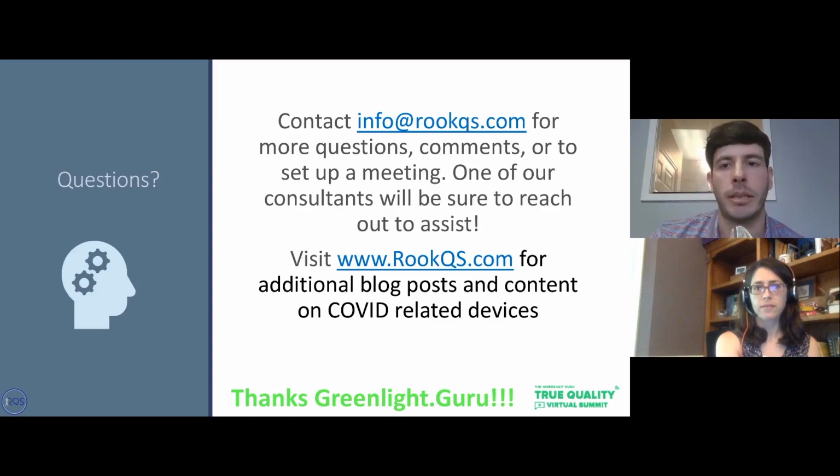So it's similar to a summary letter, but there is additional information for the IFU and labeling on there. So I think it's actually quite a bit of information. If you look at the FDA's website, they do have additional information for every type of EUA that's been granted, not just ventilators. Just like always, the FDA website can be hard to navigate sometimes, but my typical approach is to just Google search FDA EUA and see what comes up on the FDA site, and then you should be able to find it. If you have specific EUAs that you're looking for, definitely reach out to our email and we can see how we can help.